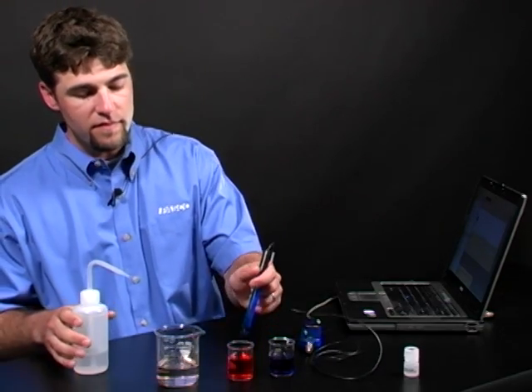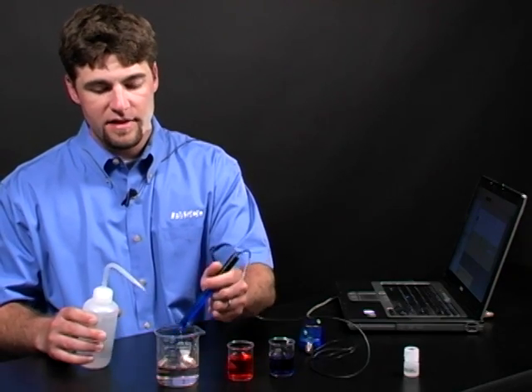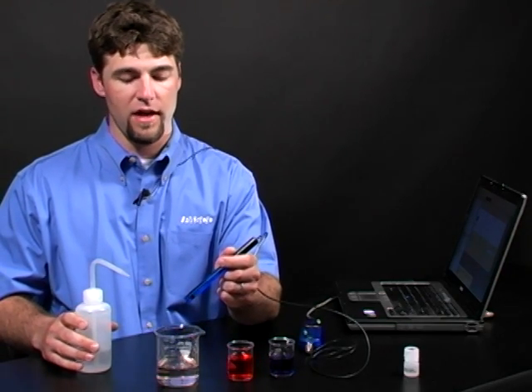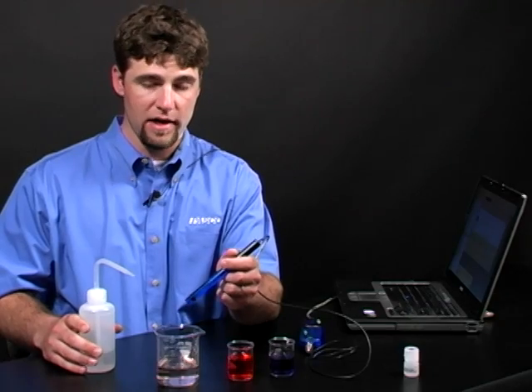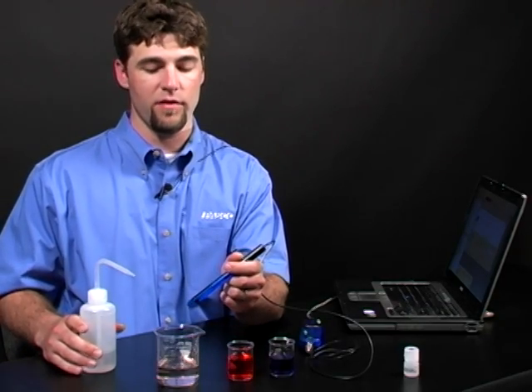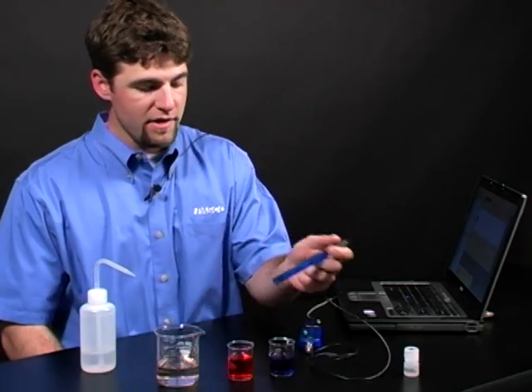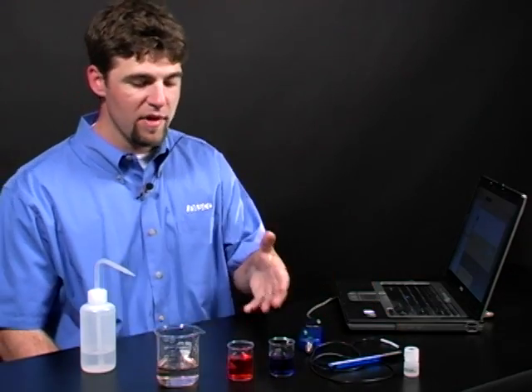measurements. It's important to note that sensors like this pH sensor have a finite shelf life and often require calibration. It's recommended that you calibrate this sensor before every experiment. It's also important to note that the calibration information that we've just recorded is not stored on the sensor itself, but in fact, in the file that you'll save after having recorded data. And it's just that easy.